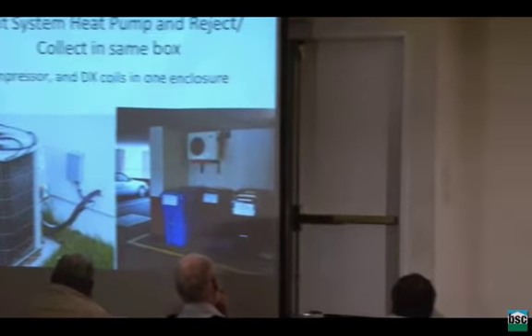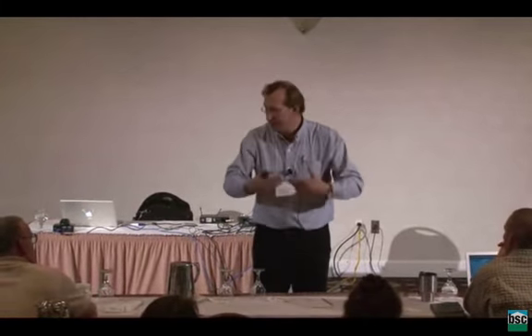If you were interested in making a heat pump that was dedicated to heating mode, not cooling, you would put the compressor in the house. Because then you'd take advantage of the heat that's created by that compressor. And so you'd have to buy a unit like that from Japan or Sweden or Denmark or Germany or Italy or China or, well, everywhere but Canada and the United States. The ones that are devoted to heating only actually take the compressor and put it indoors.